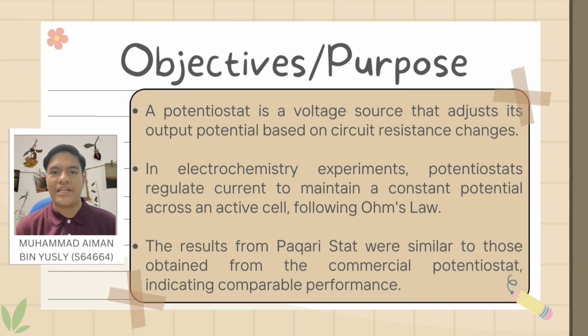Based on the article, the Paqari Stat in the system was tested against a commercial potentiostat using cyclic voltammetry with a ferrocyanide/ferricyanide redox couple and a glassy carbon electrode. The result from the Paqari Stat was similar to those obtained from the commercial potentiostat, indicating comparable performance.